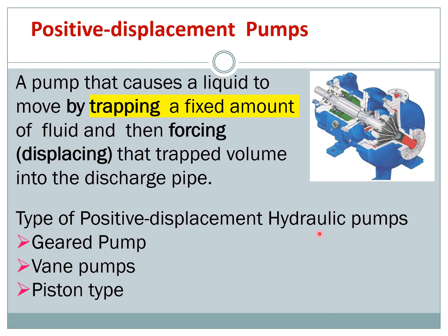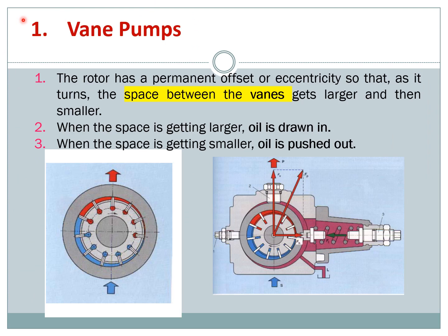There are three types of positive displacement hydraulic pumps: the gear pump, the vane pump, and the piston type pump. In the vane pump, the rotor has a permanent offset so that when it turns, the space between the vanes changes. You can see there is a smaller space and a bigger space, and this space can change from larger to smaller repeatedly.